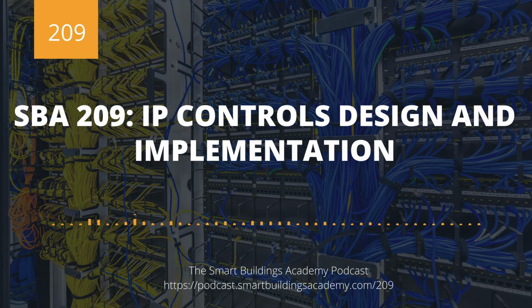Because what I have to make a decision on is this going to be a pre or a post shell setup? Because the reality is most IT gear is not going to be in the building until certificate of occupancy, or at least very close to certificate of occupancy. And if we're using IP controls and we need switches in order to connect our controls to them, then we have two decisions we can make. We can say we're going to wait for the IP controls, and that's just going to delay the commissioning of our total building, and we need the contracting tier to be comfortable with that. Or we can use industrial switches and either replace those later or integrate those into the IT network.